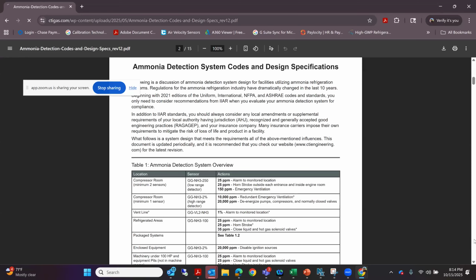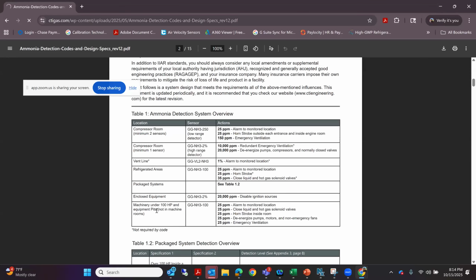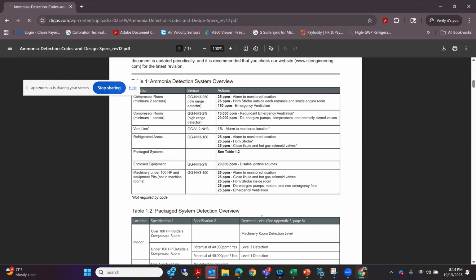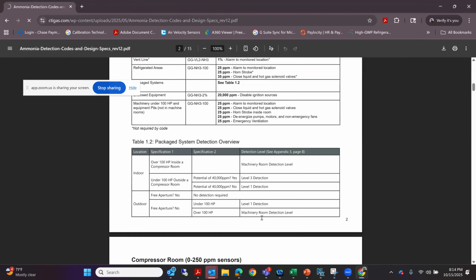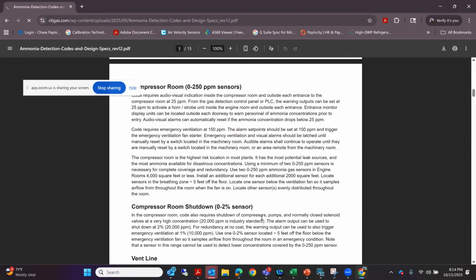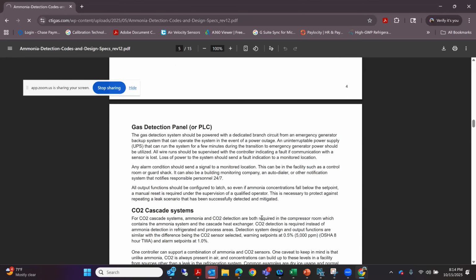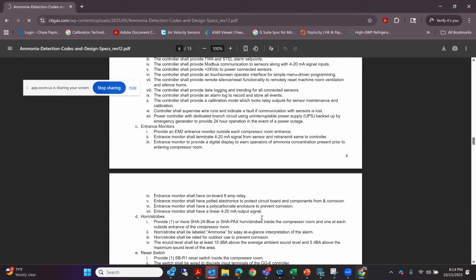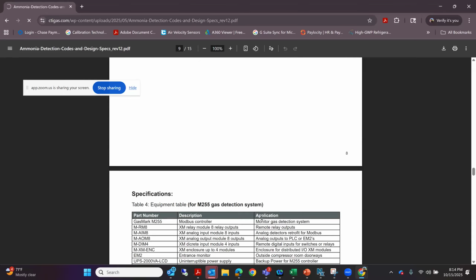with gas detection. We go over a lot of the locations of the sensors in here and what sensors should be found, what order numbers should be found in those locations, and what you'd normally see those alarm set points being in those locations throughout your facility, right? And so we cover that part of it, and then we go down and we cover the IIAR standards where they're telling us, well, what should we be doing with these systems?